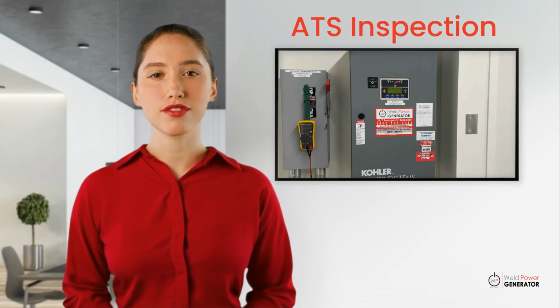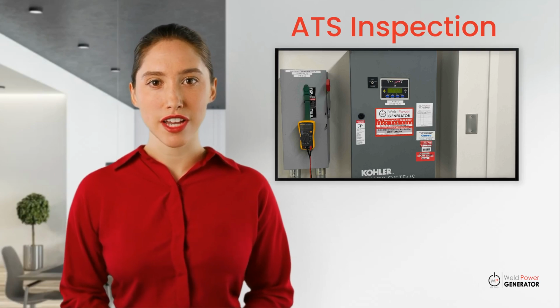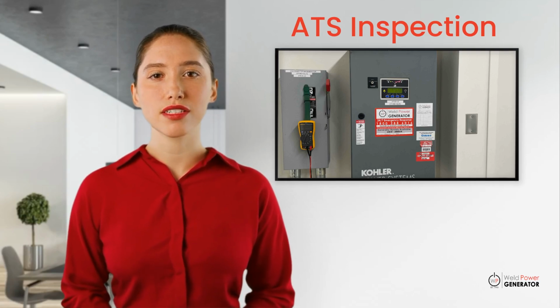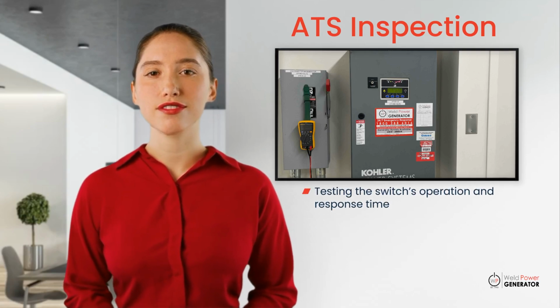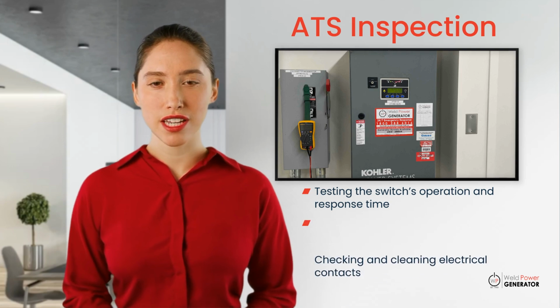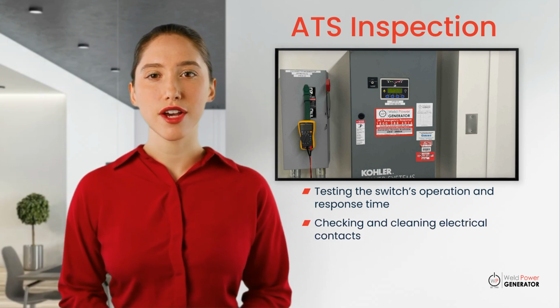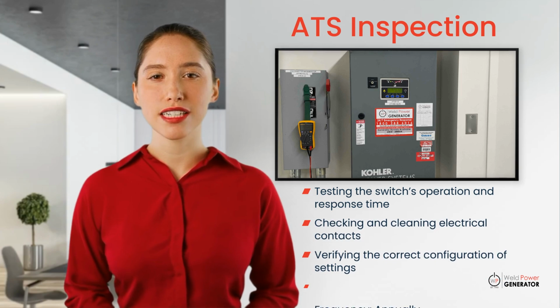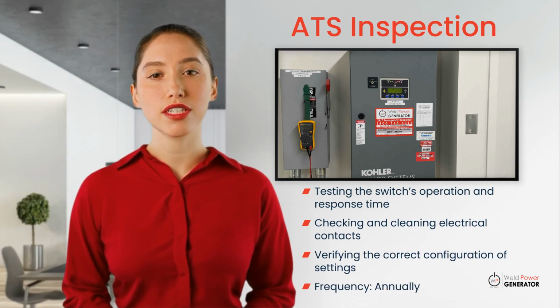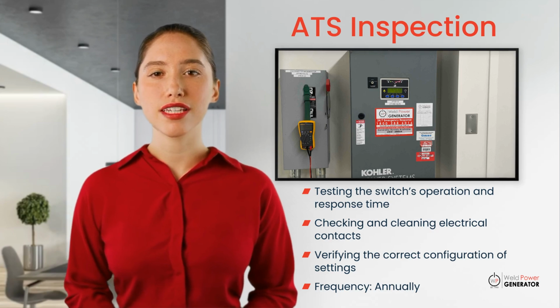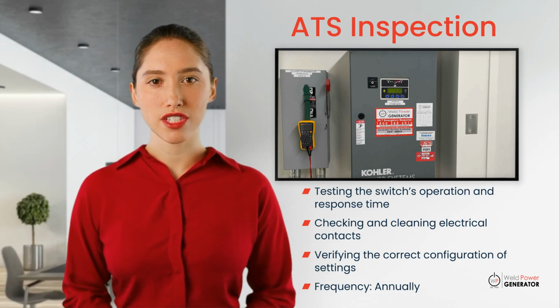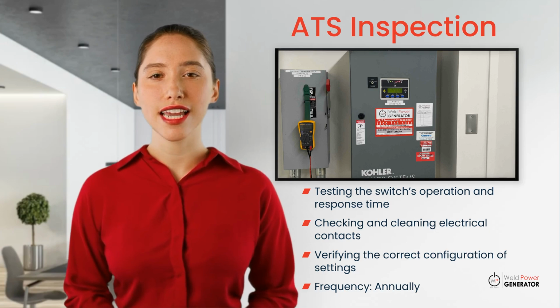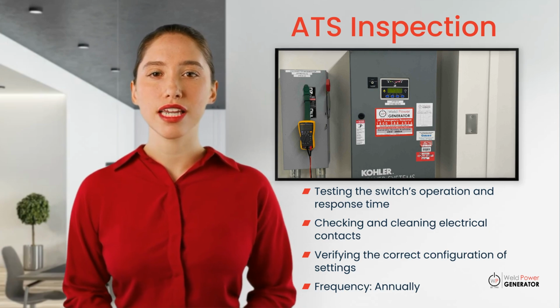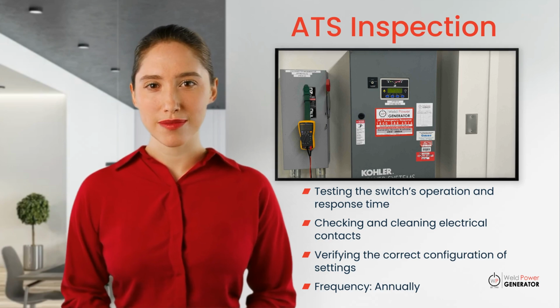The automatic transfer switch, or ATS, shifts the electrical load from the utility provider to the generator during a power outage. Maintaining the ATS involves inspecting and testing its operation, cleaning electrical contacts, and verifying the settings. ATS maintenance should be performed annually to ensure the system operates smoothly, avoiding delays when transferring power during an outage. A properly functioning ATS is crucial to the overall reliability of the backup power system.